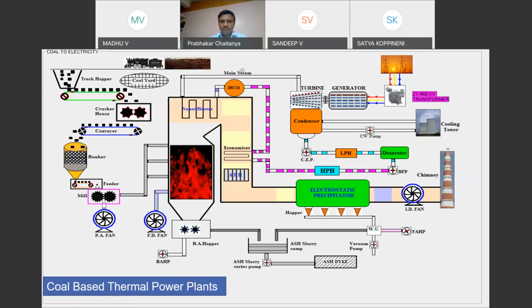Momentary load values can be met by opening the control valves, but shall be substantiated later by increasing the feeder coal flow. Similarly, for sudden load reduction, we can close the valve instantaneously so the steam flow gets reduced. Obviously the pressure will rise because we are creating a restriction, so the generator load will be immediately reduced.